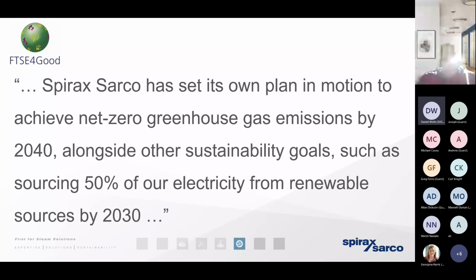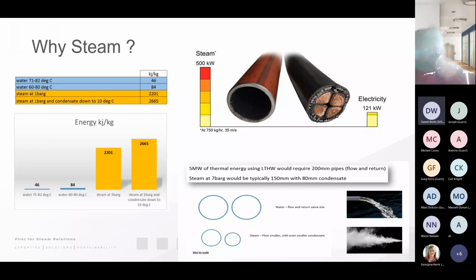So moving forwards, let's look at why steam is so very well received in so many industrial manufacturing sectors. Simply put, it's because steam is so densely packed with energy. Up in the top left-hand side of the screen, the little table really reminds us that the only way that water can give up its heat energy is by cooling down. So if we've got a kilogram of water that cools down 11 degrees in order to give up its energy to a process, well, if we compare that kilogram of water to a kilogram of steam, there's far more energy contained within the steam than there is in the water. In fact, it's true to say that there's 50 times more energy in a kilogram of steam than there is in a kilogram of water.